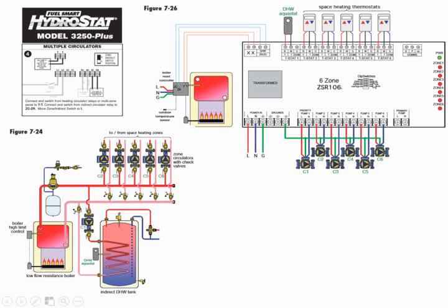Got our aquastat on zone number 1, and in this particular case, we'd have priority enabled, and when priority calls, C1 would fire. Otherwise, when any of the other space heating units call, one of these other pumps would call. And when priority calls, of course, these are all held off. So a pretty basic system here.